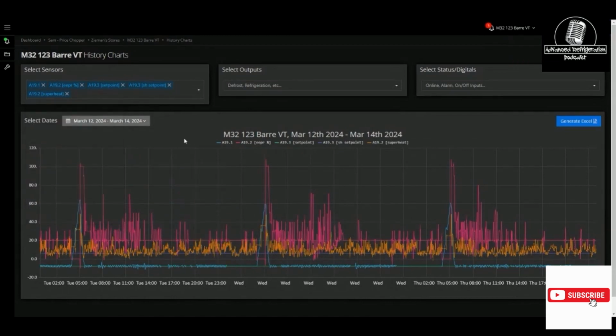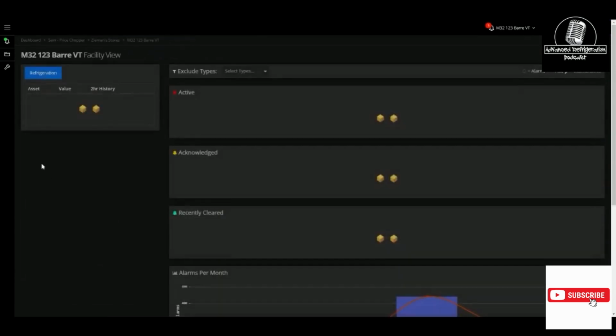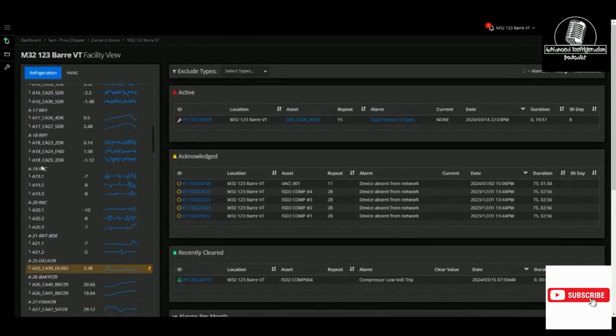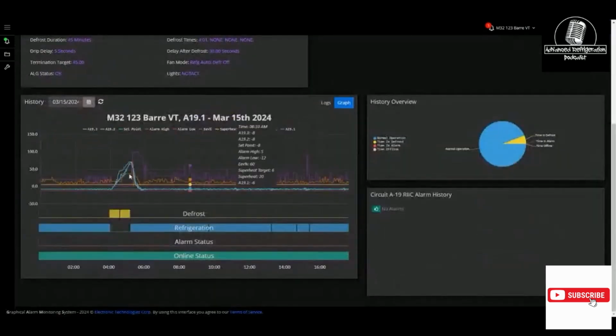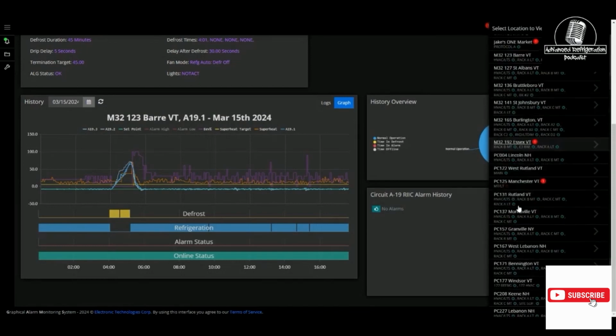And actually in this store in particular, instead of accessing the history chart for all of this, we have it right underneath the circuit. So if I go into A19.1 right here, all of it's already selected. So I can take these out here, alarm high, alarm low, whatever else. But I've got the superheat target. I can see where the superheat's trending. I can see what the temperature is on the blue line. And then the set point obviously is the green line, which is hidden because it holds set point pretty well. But I can overlay any of those outputs or inputs that come out of that 679K controller right on the history chart. So CO2 tuning, this is perfect for in that sense.